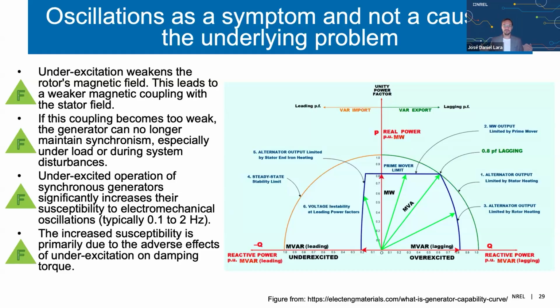But I'm going to have to, because I have so much renewables in the system that are not set up to regulate. Those units are going to start regulating voltage under-excited and also at very low levels of loading, which just worsens the situation of the electromagnetic stability of the machines. And in Kundur's book, one of the classic power systems books, it says very clearly that under-excited operation of synchronous generators increases their susceptibility to these oscillations in the range of 0.1 to 2 hertz.